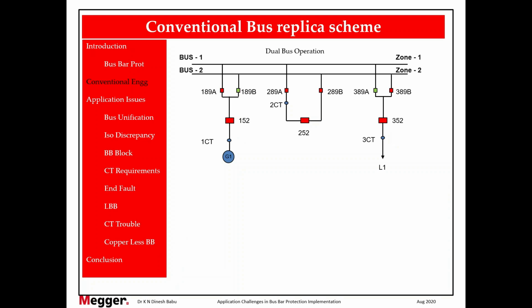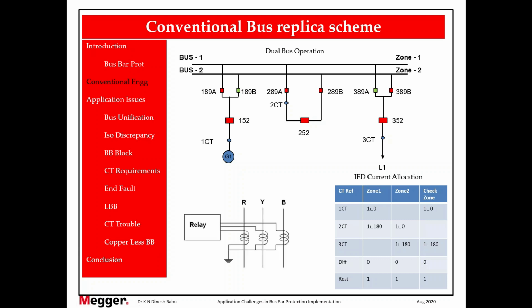Third example, feeding through the bus coupler. So current flows into bus 1, is routed through the bus coupler and flows out through bus 2, like this. What is the current direction? This is the CT allocation and this is the CT star point earthing which we discussed earlier. Now let us understand the concept. 1 angle 0. Yes, it is flowing towards the bus. CT2, assume CT2 is earthed towards bus 1, but current is flowing away from bus 1. That means it is 1 angle 180. So 1 angle 0, 1 angle 180. Perfect.